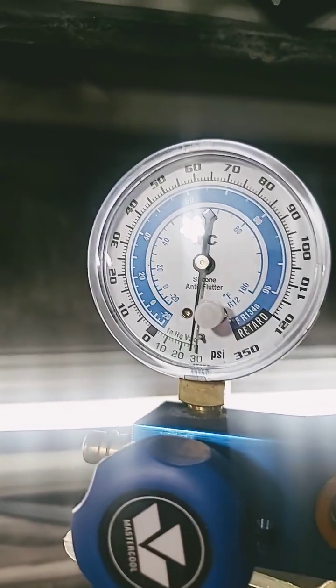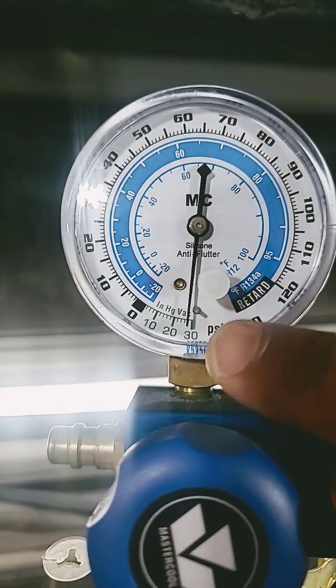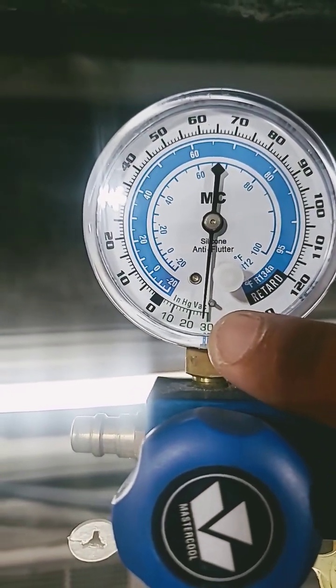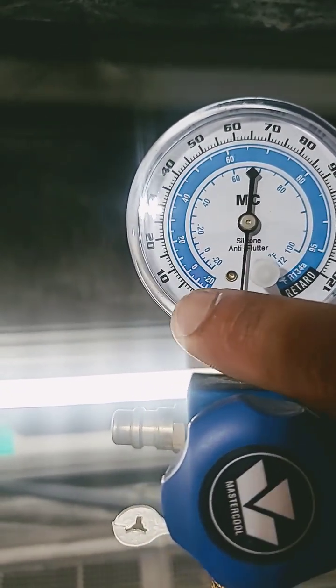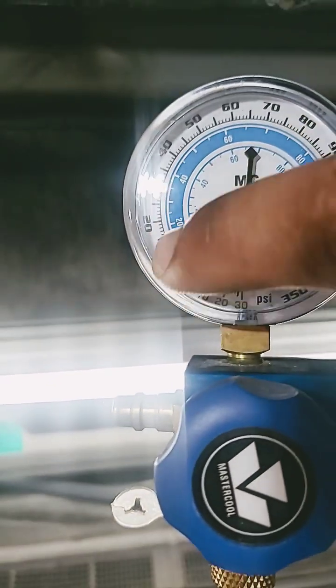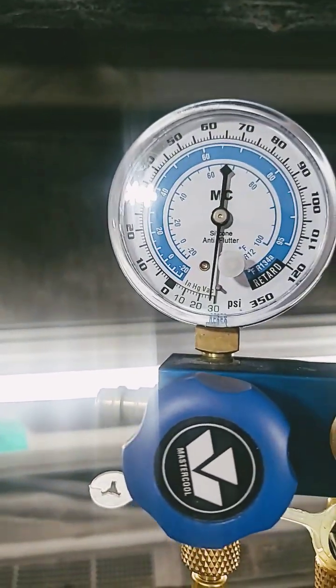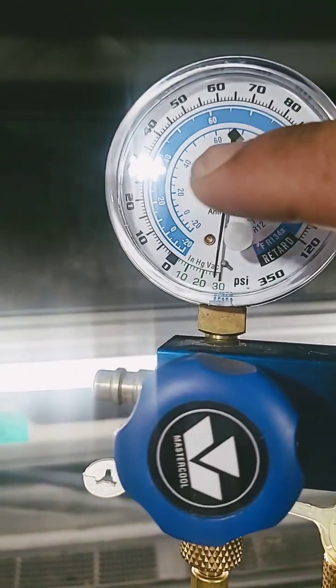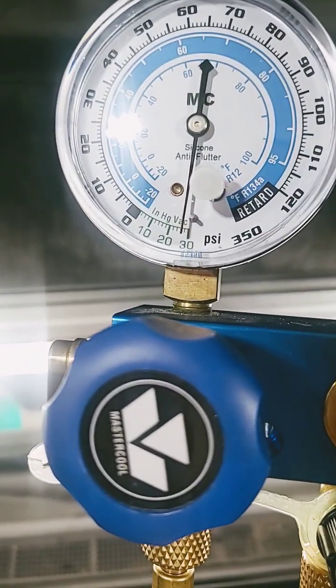Now, if you have a leak in your system, your gauge is not going to read 28 to 30 inches of mercury. Your gauge is going to stay up here, okay, around here. Because if you have a leak in your system, the pump can't pull a vacuum on the system.